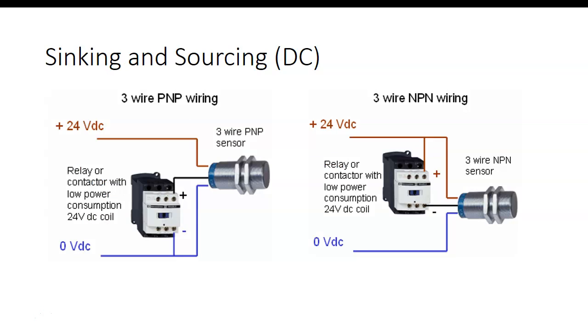So this is a standard color code that came out for a while. These are our DC sensors. So this will be a control relay. The brown wire hooks up to what? On DC it hooks up to plus DC. The blue wire hooks up to what? Zero, your minus, or 0 low. And then your signal wire is black.